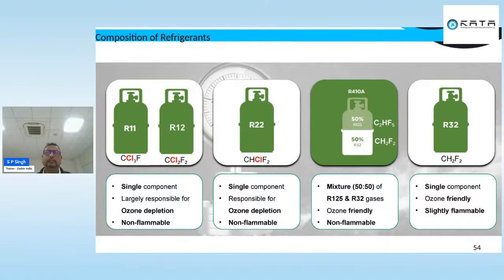It is very easy to charge this refrigerant, and it is slightly flammable. It comes into the A2 class. There are different classes for flammability. So it is slightly flammable compared to propane. Propane is more highly flammable; it comes into the A3 class. There are different classes mentioned globally. So R32 is slightly flammable, but still it is an ozone friendly refrigerant, and global warming impact is also quite less compared to 410 or R22.